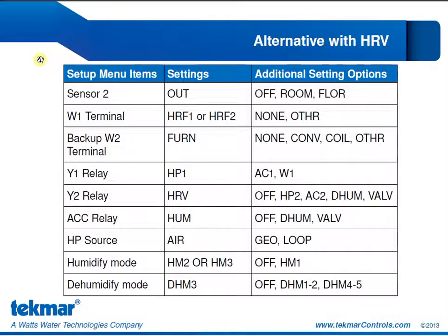The essential settings for this. Now in this case, we absolutely require an outdoor sensor, because if you remember, the HRV can only be operated if the outdoor temperature is at least 5 degrees below the indoor dew point. So we're going to configure sensor 2 for our outdoor sensor. Our W1 terminal will be set to HRF 1 or HRF 2, depending on the mass of the radiant. Our backup W2 terminal, that electric backup strip, will be set to furnace for the fan operation.